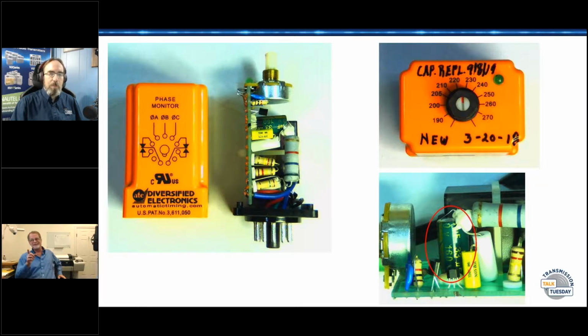As you can see the dates on that one, it was put into service in March of '18, and it failed in September of '19, so a year and a half later. We have a shelf full of these, but every one I've repaired and put back in transmitters is still working, 2 or 3 years later, still going.